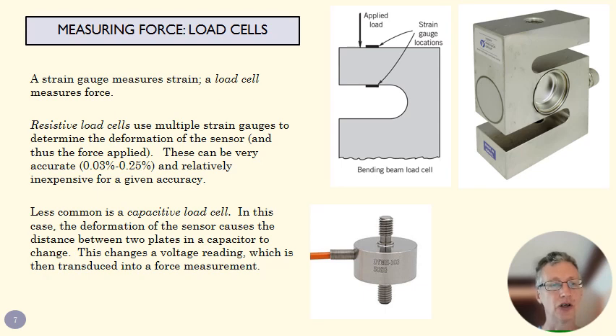There are other kinds of load cells. One's called a capacitive load cell, which is pretty cool because it presses some plates together. A capacitor changes its capacitance when the two plates of the capacitor get closer together or farther apart. That allows us, if we set up a circuit, to measure any changes in the capacitance of our load cell.